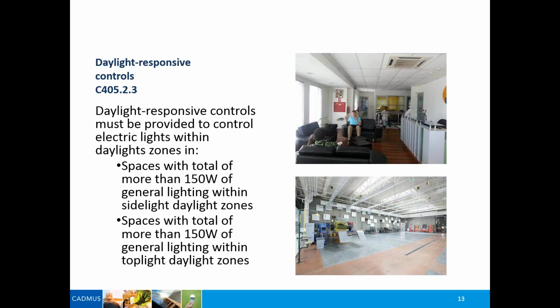For a typical skylight, the way it is calculated is you take the dimension of your skylight, and you also have your ceiling height, and it's 0.7 times the ceiling height. So basically 70% of your ceiling height, and you add that dimension to each side of the skylight. For example, if I have a 10-foot ceiling and a 4x4 skylight, 0.7 times 10 feet is 7 feet. I add 7 feet to each dimension of the skylight. So when I project that daylight zone down to the space, it's basically an 18 by 18 foot area on the floor that becomes my daylight zone, and all the lights in that daylight zone have to be controlled by an automatic daylighting control. So again, you're projecting your daylight zone down to the floor area.